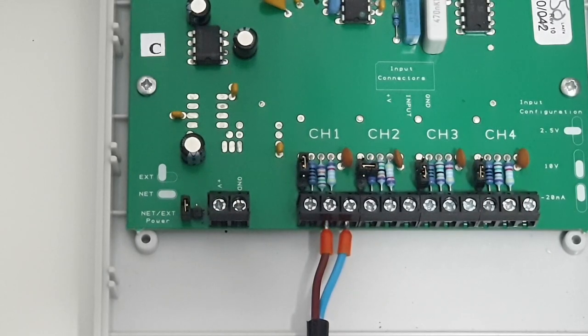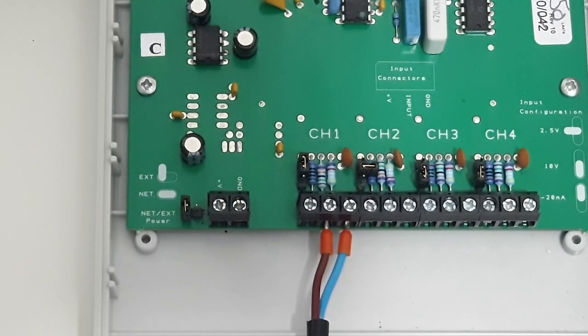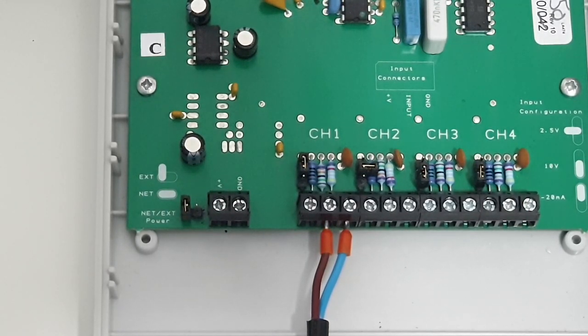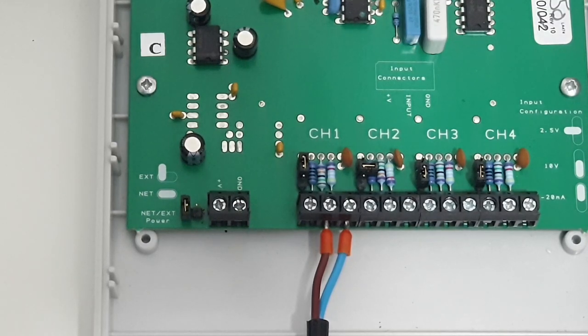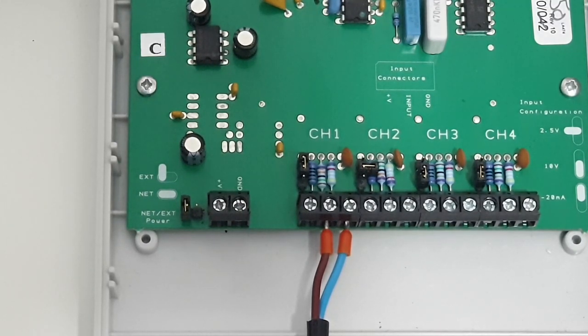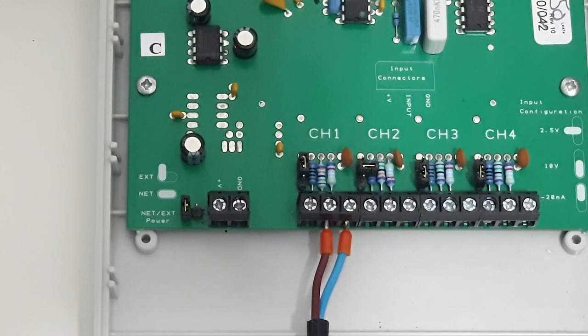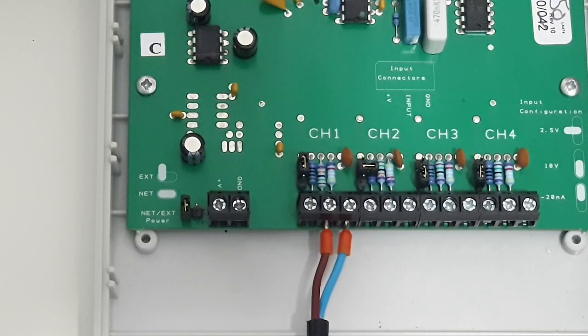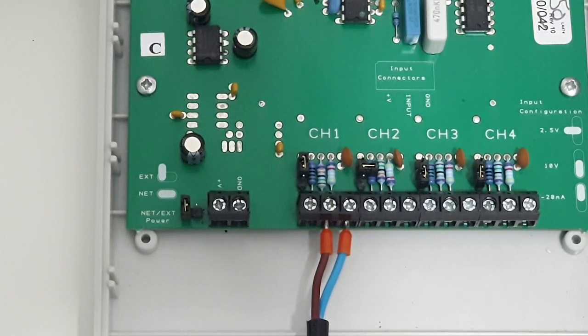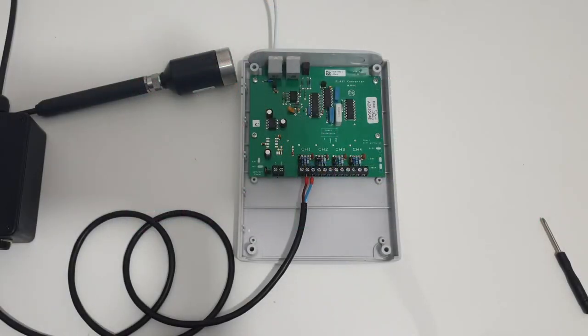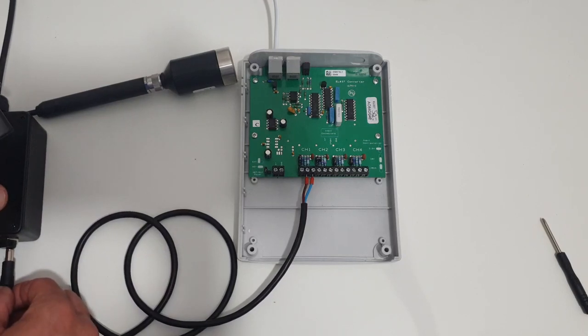Now it's worth noting that different 4 to 20 milliamp transducers can be wired differently, depending on the way they're designed. They could be self-powered or loop powered. They come in two wire, three wire, and four wire. But in this particular case, it's quite simple. It goes into the input and ground.